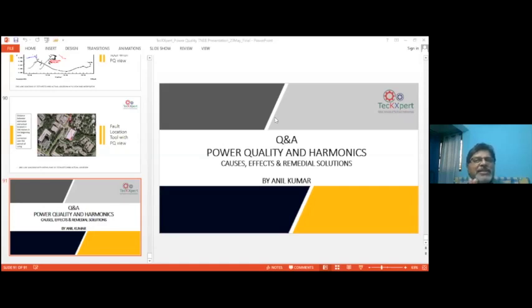My simple submission is, there is no easy computation for calculating the source of harmonics, because harmonic is a highly time varying function, and the phase angle calculations you are doing are frequency domain calculations applied to a time domain phenomenon, so it becomes a mismatch. So it's not easy to exactly predict. Yes, but you can predict it if you have multiple analyzers or meters installed at multiple points, with data exchanged at a common place and phase angles evaluated at multiple points, and see how the harmonics are flowing at multiple nodes, and you can conclude, yes, the source is here. But if you put one PQ meter or one PQ analyzer and try to find this out, you may or may not be accurate in your calculation.